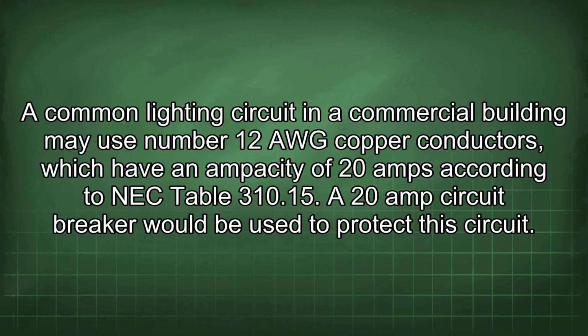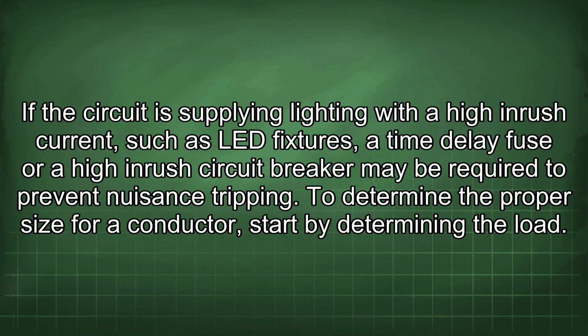A common lighting circuit in a commercial building may use number 12 AWG copper conductors, which have an ampacity of 20 amps according to NEC Table 310.15. A 20 amp circuit breaker would be used to protect this circuit. If the circuit is supplying lighting with a high inrush current, such as LED fixtures, a time delay fuse or high inrush circuit breaker may be required to prevent nuisance tripping.